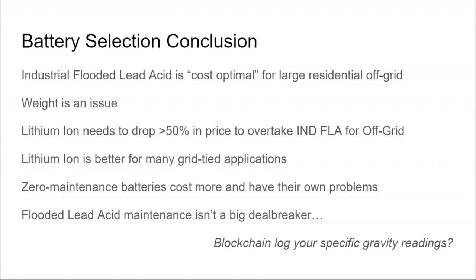Zero maintenance batteries: the biggest surprise for me is I would think a zero maintenance battery would be the better choice by far. What surprised me is that the battery you have to maintain will also last longer than a sealed battery. But that's kind of a moot point, because as lithium ion becomes the dominant battery technology, all batteries will be sealed going forward, other than big utility scale batteries.